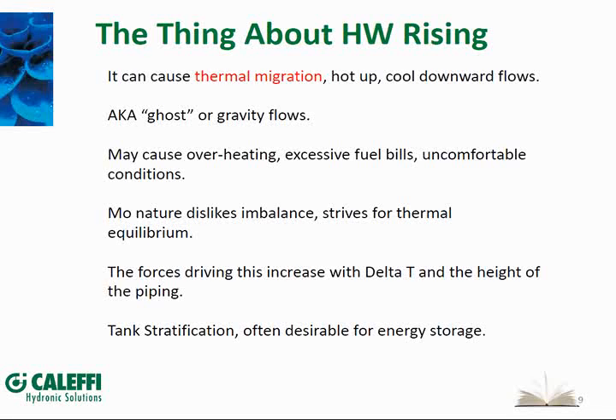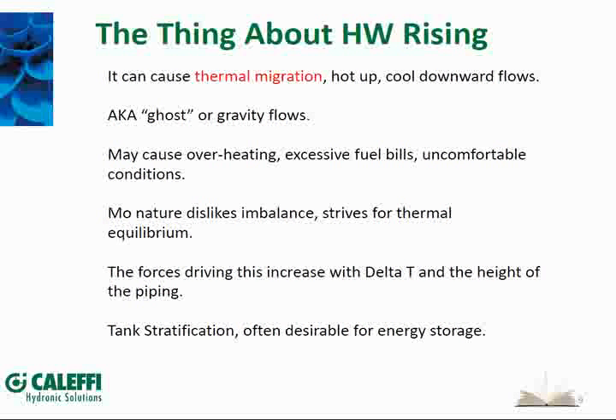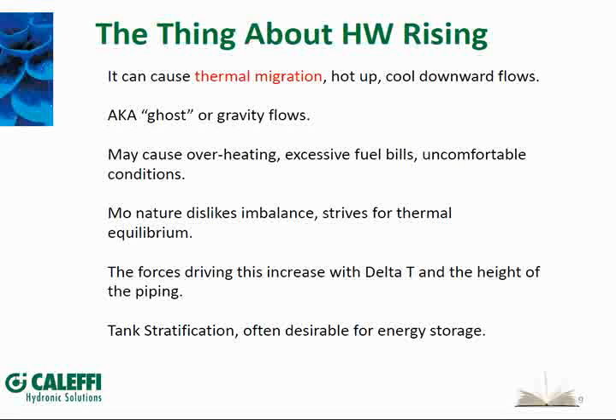There are times when thermal migration is desirable. One example is stratification in a domestic water storage tank — we want hot water to rise to the top. The control thermostat near the bottom shuts off at maybe 140°F, but we can stack more energy in the tank by allowing it to stratify and letting hot water migrate up to the top.